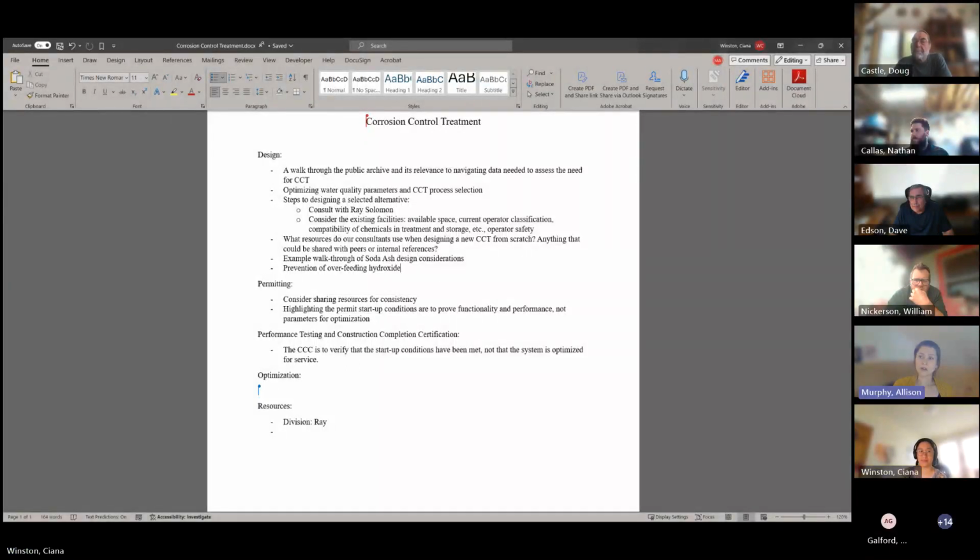Allison? I'll just offer that we always ask more questions when it's sodium hydroxide as opposed to soda ash. A lot of concerns come with sodium hydroxide storage and operator safety. We want to see a lot more when it comes to that, because the changes to pH can happen more rapidly.